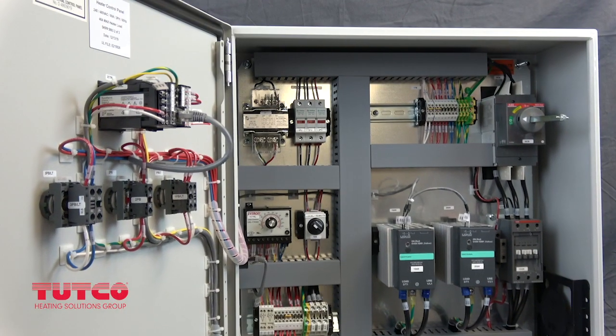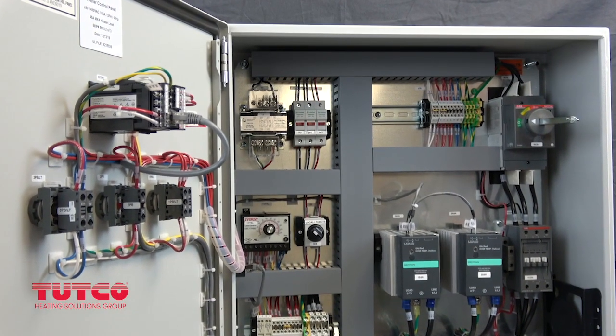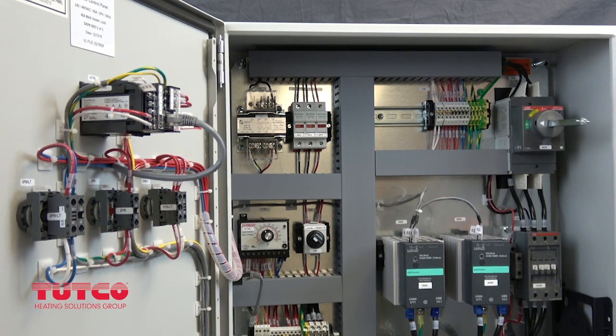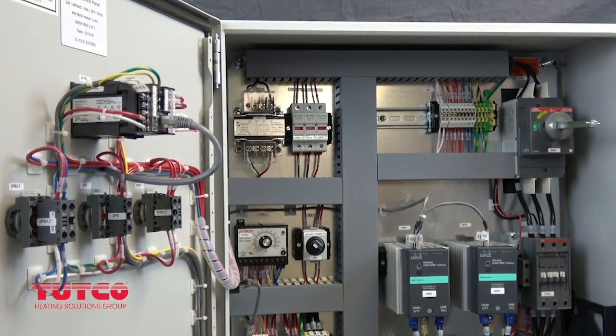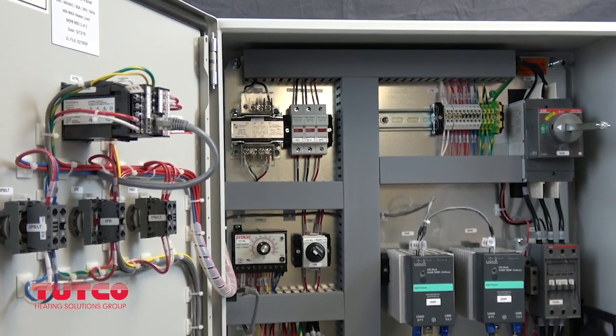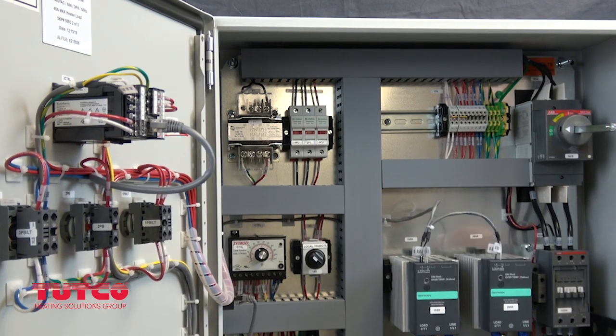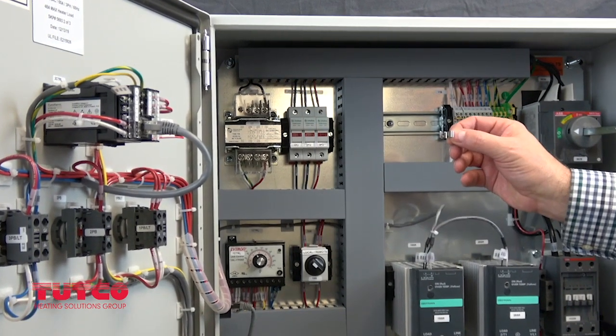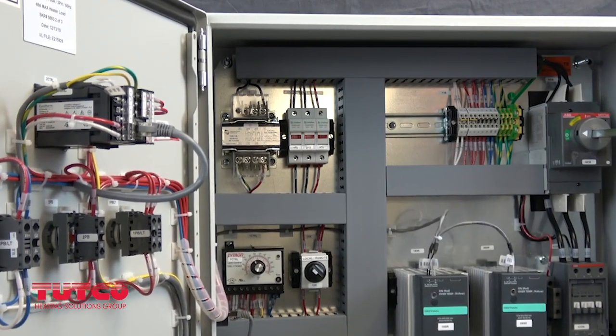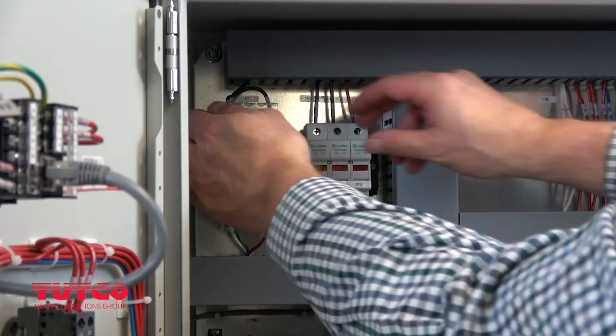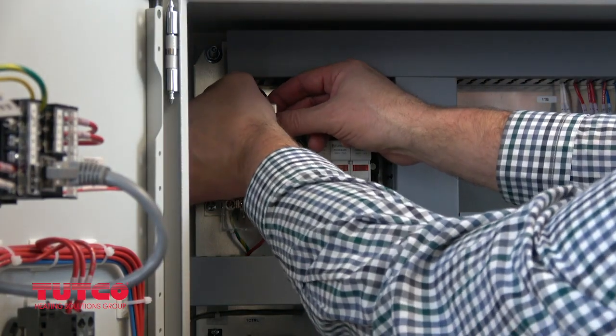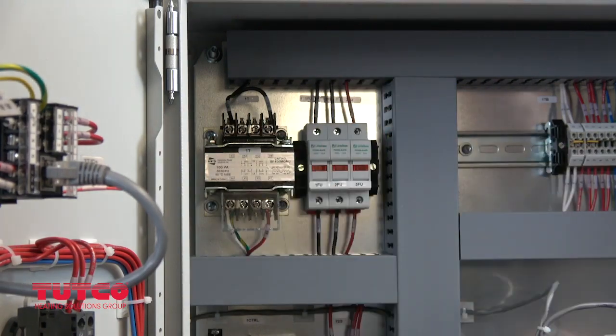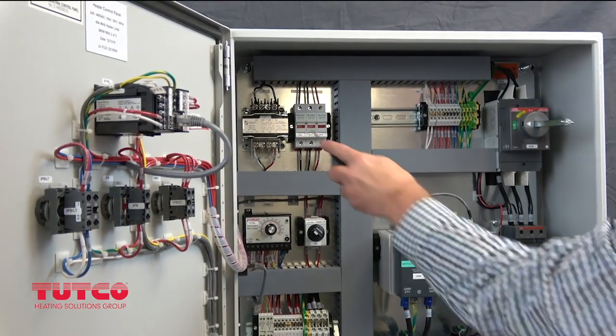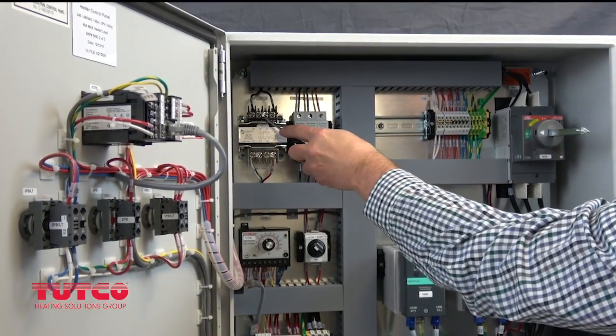The next step is to verify that the transformer clip is in the right position for the control voltage connected. The unit should be set at 480 volt from the factory as default. If 240 volt is needed, install the spare jumper clip to change the transformer from 480 to 240 volt. The first thing required to do is to remove the transformer wire safety cover. Refer to the labeling on the transformer for all input connections.